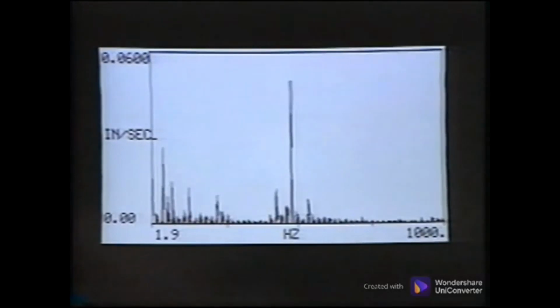The sound level increased because a new batch is being dumped in. A peak is climbing out of the noise floor of the spectrum. This is the gear mesh frequency. Notice that there are no sidebands of much amplitude. The only peak is the gear mesh frequency.